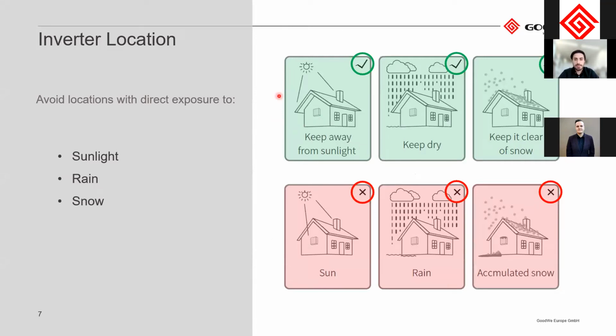Also, some advice and recommendation on how to install it or where to install it. This is also included in the manual, of course. But what's important is the inverter, at least, all inverters have IP65, at least a minimum rating, so they can be installed both inside and outside. But even though they can be installed outside, we do recommend that you protect them a bit from direct sunlight and also rain and snow. So keep them under a small roof or something, and also in the shade, because this will also increase the lifetime of the inverter and make sure that they don't overheat.